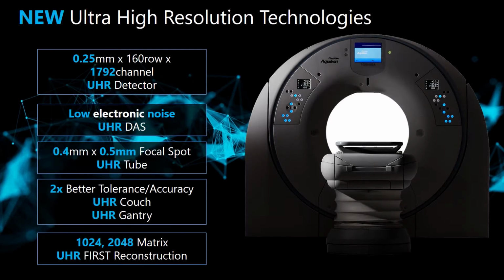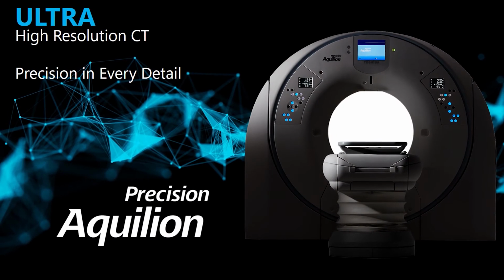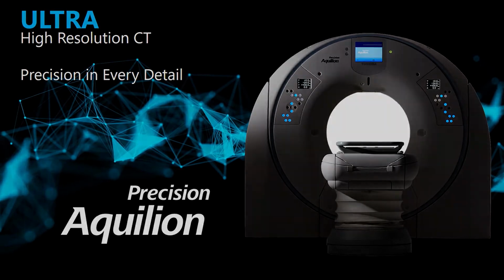The Aquilion Precision also features a totally redesigned X-ray tube, which has the industry's smallest focal spot at 0.4 by 0.5 of a millimetre. Coupled with this is a brand new ultra-high resolution CT DAS, as well as an ultra-high resolution couch, which has a 200% improvement in tolerance and improved accuracy. A new reconstruction technology to enable reconstruction at 1024 and also 2048 matrix sizes for ultra-high resolution imaging. Canon Medical Systems demonstrates its deep commitment to technology and innovation, and with this product, we are very excited to launch into a new era of CT imaging at light speed.